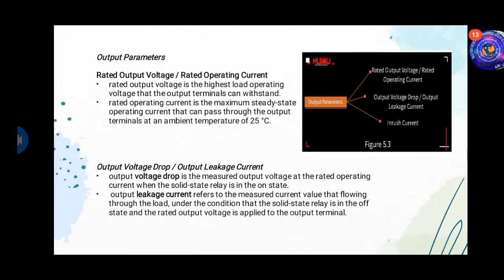Output parameters: rated output voltage or rated operating current. Rated output voltage is the highest load operating voltage that the output terminal can withstand. Rated operating current is the maximum steady state operating current that can pass through the output terminals at an ambient temperature of 25 degrees Celsius. Output voltage drop or output leakage current: the output voltage drop is the measured output voltage at the rated operating current when the solid state relay is in the on state. Output leakage current refers to the measured current flowing through the load when the solid state relay is in the off state.